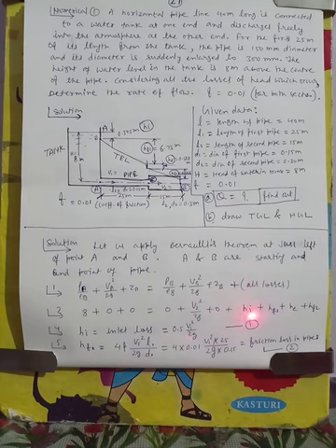First, inlet loss HI at the entrance of the pipe, plus HF1, the frictional loss in this 25 meter pipe, plus HE, the enlargement loss, because here the pipe is suddenly enlarged from 150 mm diameter to 300 mm diameter. And again in this pipe there will be frictional loss, HF2, the frictional loss in this pipe 2.